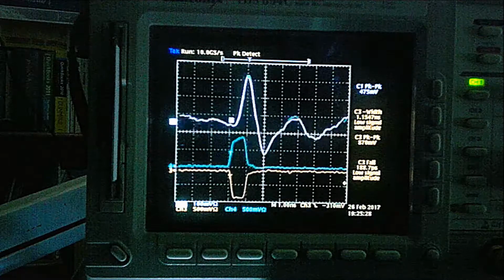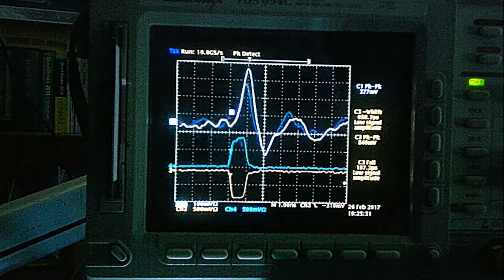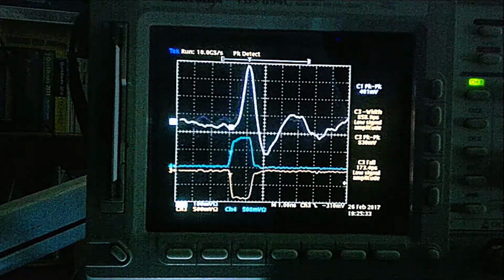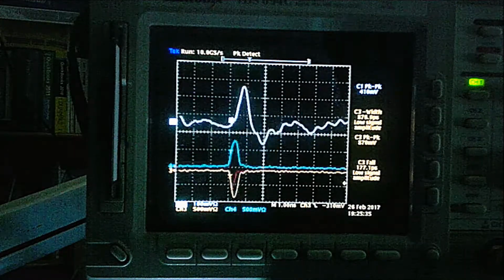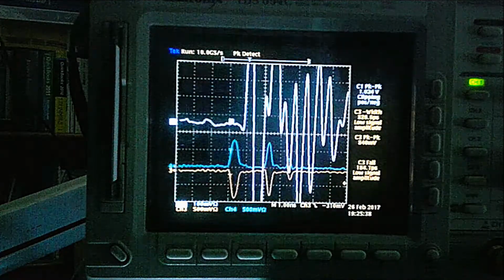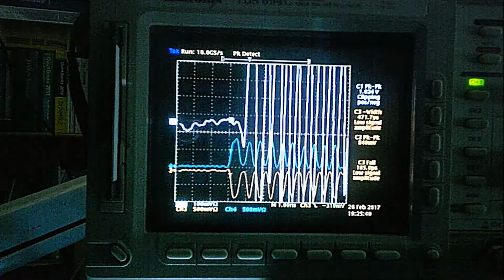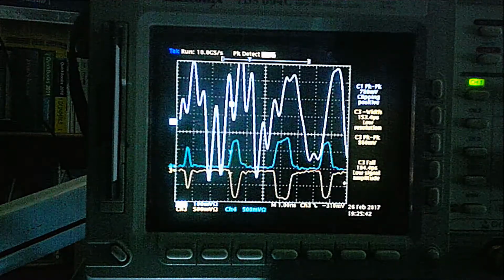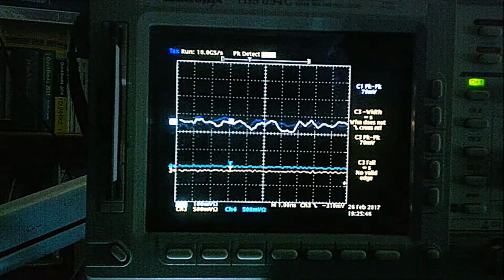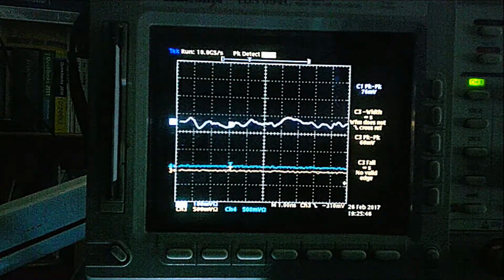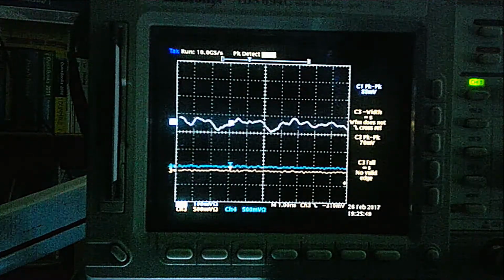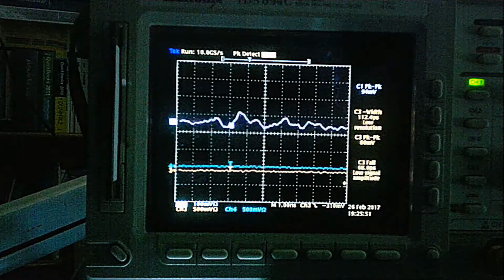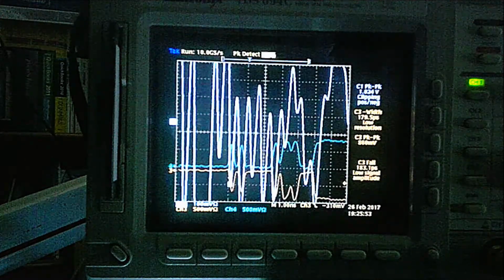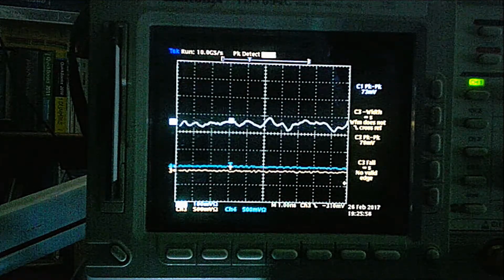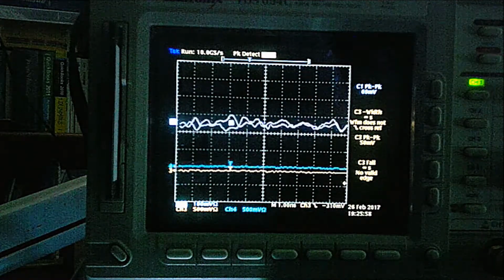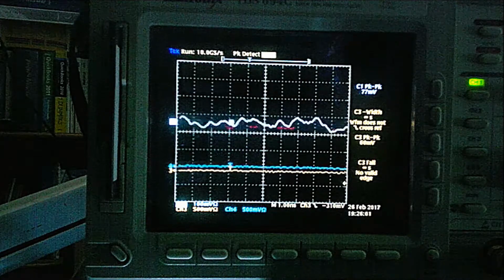How do we know we're not getting noise? I'm going to turn off the high voltage. When I do that, there will be a burst of noise. It takes up to a minute for the high voltage power supply to bleed down and every single bit of noise to get out of the system. As you can see, the bottom trace is not triggering at all, which means that there is no false photon count output when there's no noise from the system. And it can take, like I said, a minute for the noise to quiet down.